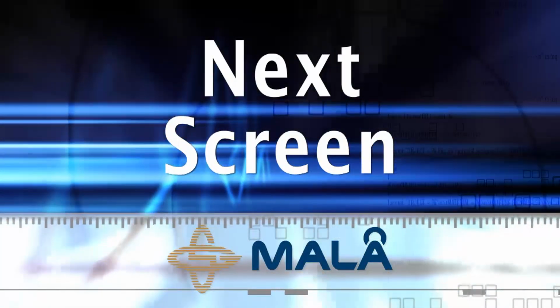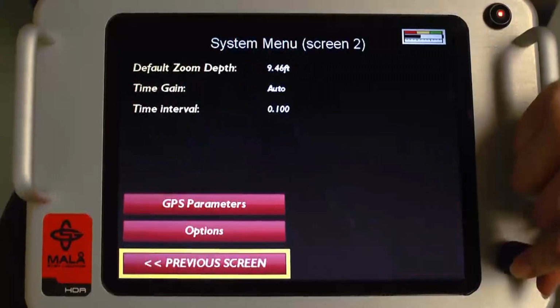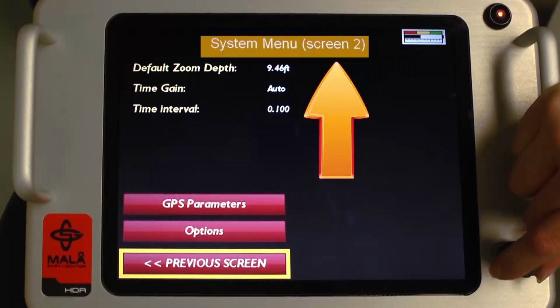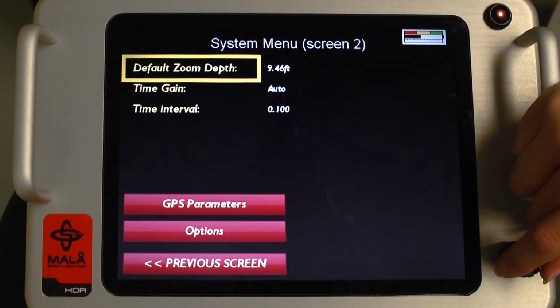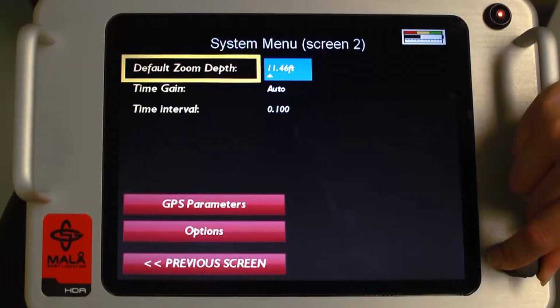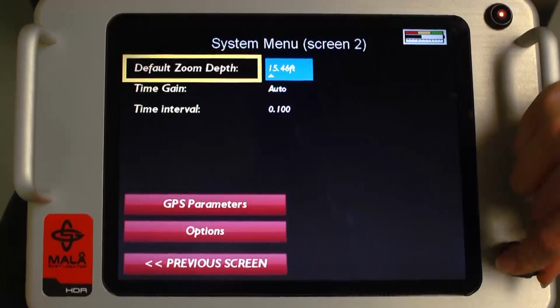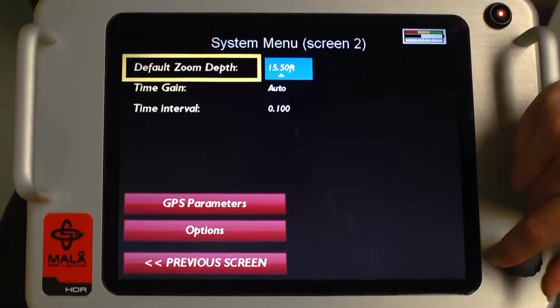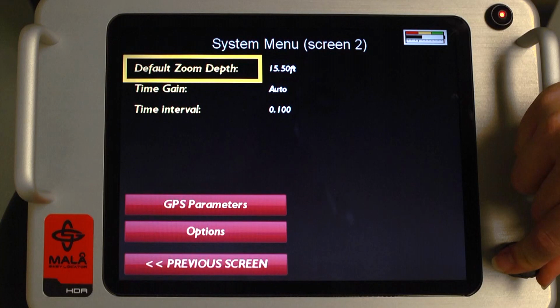Next screen. Depress Next Screen to open System Menu, Screen 2. In Screen 2, the user can adjust the default zoom depth of the system. The default zoom depth simply defines the range of depth window, or the maximum depth range a target may be detected. Please note that this scale is dependent on the soil velocity setting. In a later segment, soil velocity calibration procedures will be covered. Also, the depth window maximum does not necessarily mean quality data is achievable to that maximum. Soil conditions vary greatly and affect the maximum penetration of GPR signals.